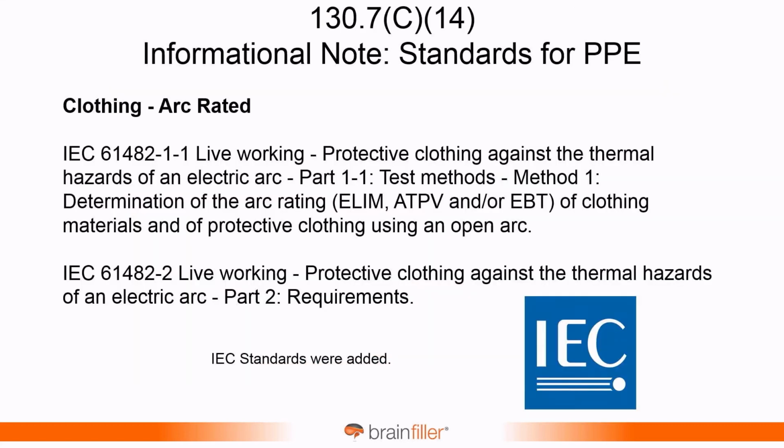This was another change. I actually got kind of involved in this one. For PPE testing and arc-rated PPE, historically, NFPA 70E has referenced ASTM standards. And the last cycle, all of those standards were moved to a table referenced by an informational note.